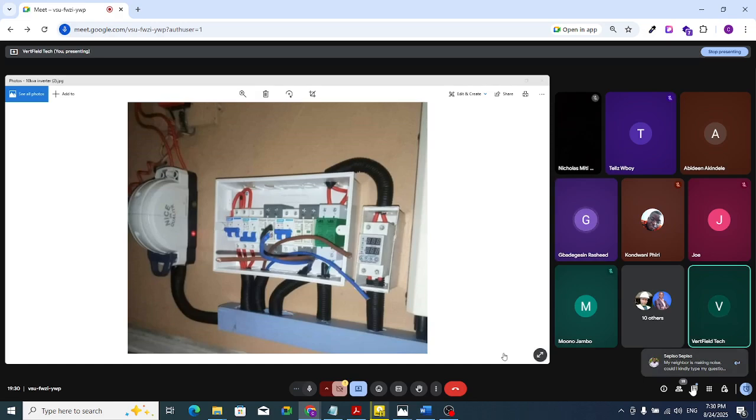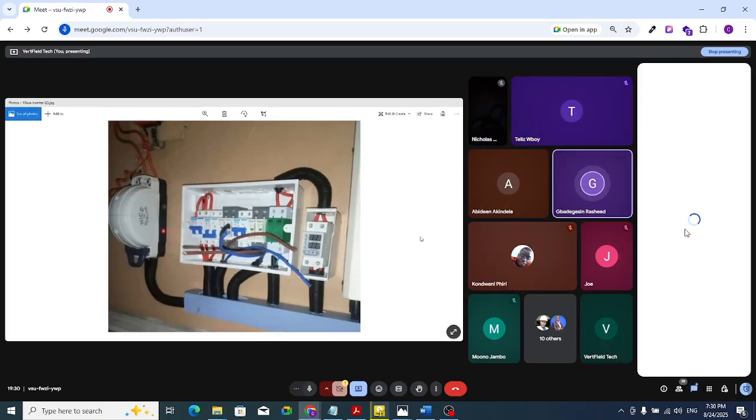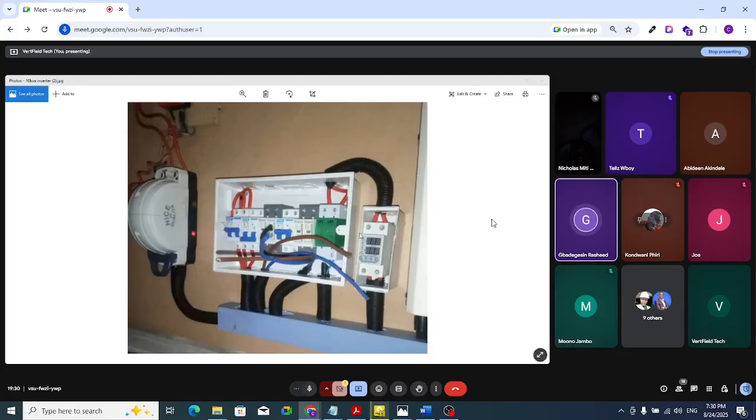Yes, I'm Daddy Deshin by name, Lagos, Nigeria. So my question is based on the safety aspect. You know, for instance, whereby the connection has been done, and truly, we found out that the inverter is shocking. We put our tester, and we found out that it shows currents from the tester, and you know we have rounded up the installation, and we now found out that there is no proper earthing in that building. So what is the advice that you can give in order to solve that kind of problem?